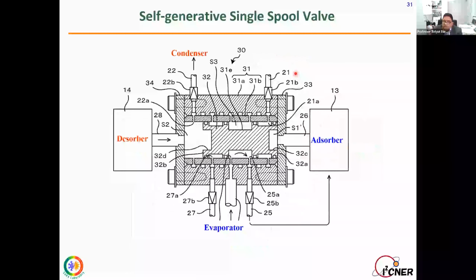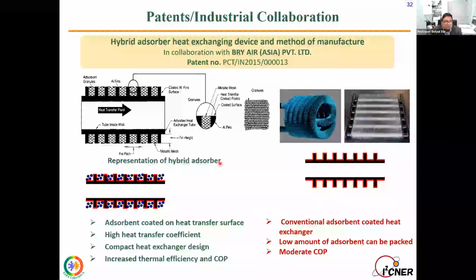In the opposite cycle, when this bed becomes the adsorber, pressure is low in this bed and high pressure is in the left side bed. So this vapor pushes our spool so that vapor from this bed through this channel can reach the condenser. On the other hand, vapor from the evaporator through this channel can go to the adsorber bed. So we are getting continuous adsorption and desorption processes, but we are using only one valve instead of 4 valves here. The valve is very promising. In this case, it is only about the size of one A4 paper.